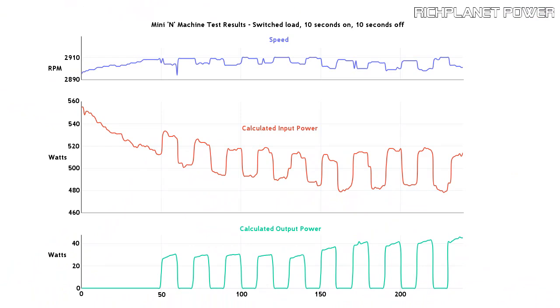So I waited until the current stopped climbing and it seemed pretty fixed, and the input power seemed pretty fixed as well. I waited for those levels to settle. Then I opened the circuit breakers and instantly removed the load and measured the difference in the power levels immediately before and immediately after the switchover.